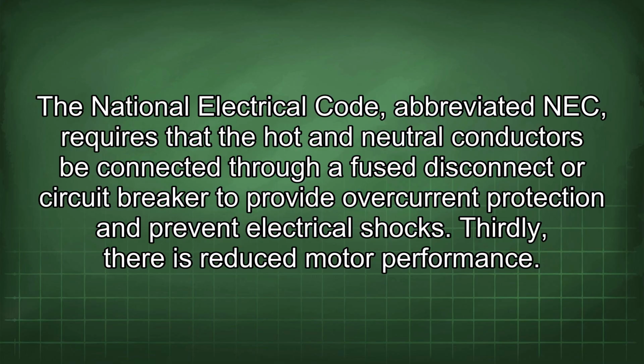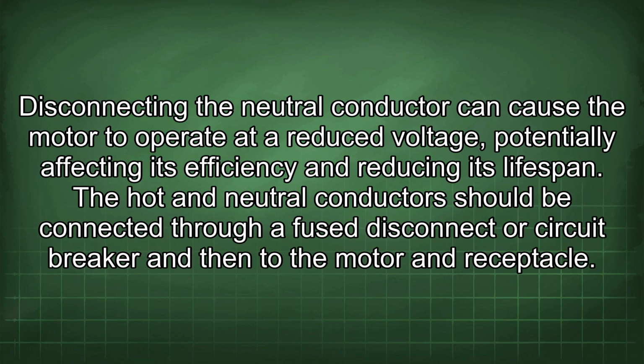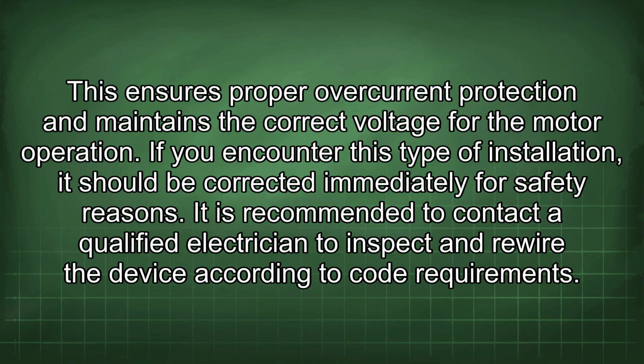Thirdly, there is reduced motor performance. Disconnecting the neutral conductor can cause the motor to operate at a reduced voltage, potentially affecting its efficiency and reducing its lifespan. The hot and neutral conductors should be connected through a fused disconnect or circuit breaker and then to the motor and receptacle. This ensures proper overcurrent protection and maintains the correct voltage for the motor operation.